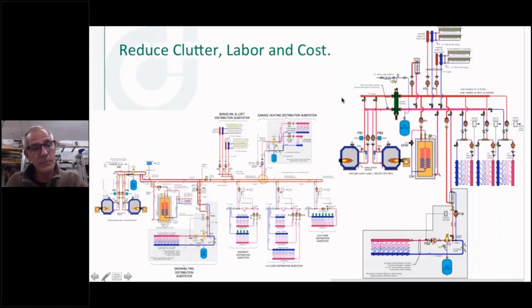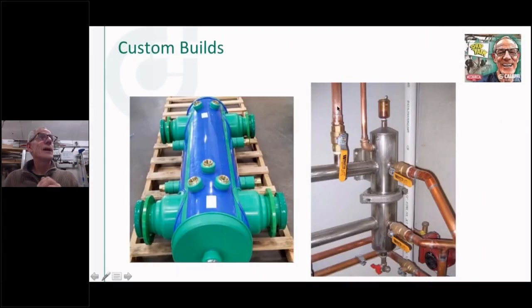You just got to look, they're trying to be clear when they give you information on the pressure drop. Usually they'll put charts in there and say, okay, if you use this pump, you've got this much head available to do your distribution. If it's beyond that, they really want you to go back to either primary, secondary, or putting in a hydraulic separator. We're pleased to see that. What am I doing for time here? More and more manufacturers are actually putting both drawings in their installation manuals. They'll show you primary, secondary is an acceptable way to do that. Hopefully they've got the expansion tank and everything in the right place in those drawings. Or they'll say, hydraulic separator is another option to make sure that we've protected the boiler.